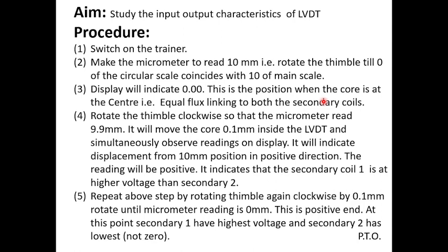First we make the position where the display reading is 0. Here the 10 millimeter position is this. Now we go in the clockwise direction. If we go clockwise, the core will move more and more toward the secondary coil, and by rotating like this it will reach the highest point of secondary coil 1.